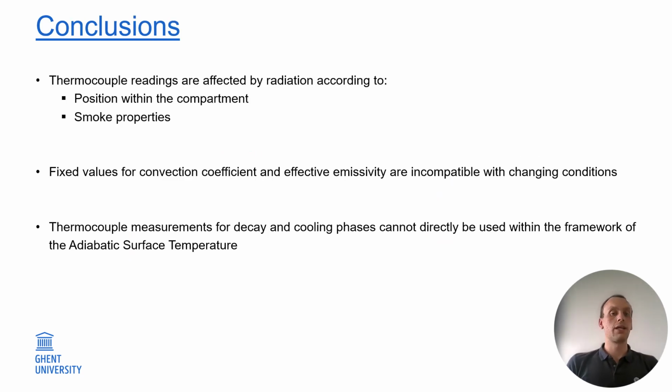Now, to conclude, we can say that thermocouple readings are affected by radiation according to their position within the compartment and the optical thickness of the smoke. Fixed values for convection coefficient and effective emissivity are incompatible with changing conditions, and thermocouple measurements cannot be used as a validation for the adiabatic surface temperature in the fire decay and cooling phases.